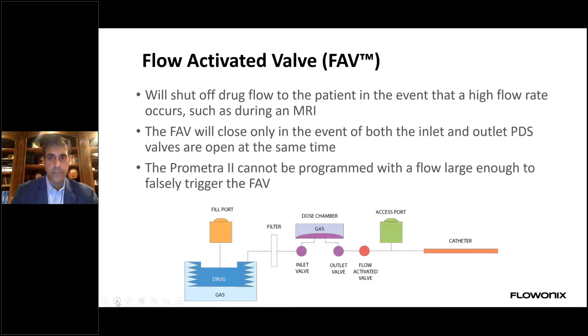The flow activated valve will only close in the event that both the inlet and outlet valves are open at the same time. So even though the Prometra II pump has this flow activated valve to prevent flow of medication from the reservoir to the patient, Flowonix several years ago took some additional steps to adopt a protocol to ensure patient safety during an MRI, essentially.